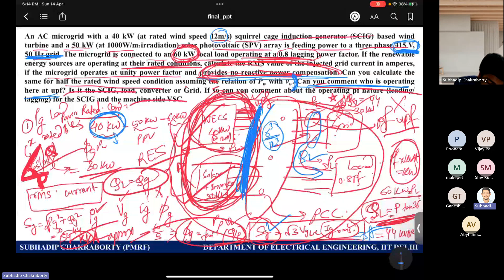Okay, because it is related cubically. Other things same. So now wind is pushing 5. Solar is 50. What is the value of IG, sir? 75 amps. 75.12 amps. Yes. Now you see, for the half the rated wind speed, the wind power decreased to 5. The wind is pushing 5, solar is pushing 50. Then can you tell me what is the power injected to the grid? It is minus 5 kilowatts, right? Means grid is supplying active power to the load.